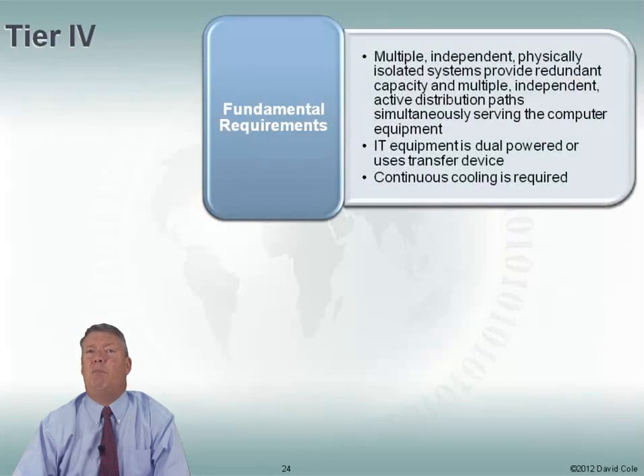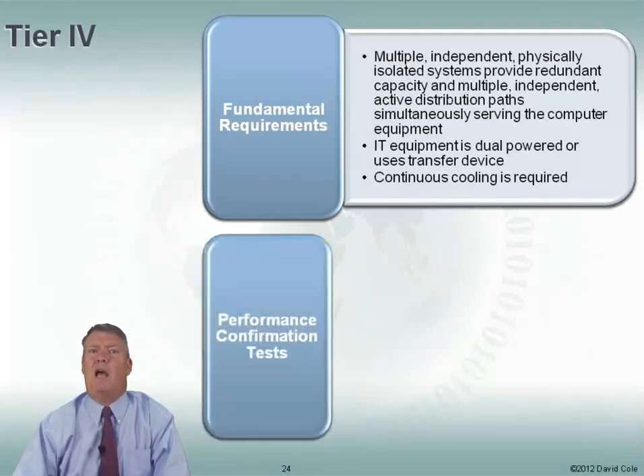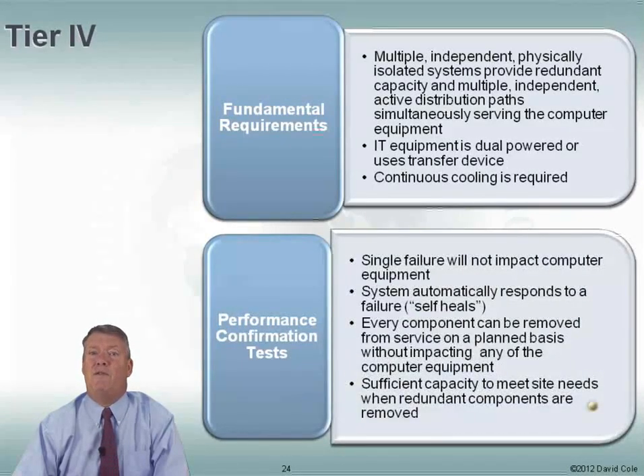Let's move to Tier 4. Now I have multiple independent, physically isolated systems. That means I've got enough capacity to take any piece of equipment out, and I've got multiple distribution paths, meaning that no matter what I do, my IT equipment is going to stay up. I have continuous cooling to stay cool even when I take systems down. As a result, a single failure should not impact my computer equipment, and every component can be removed on a planned basis without impacting anything.